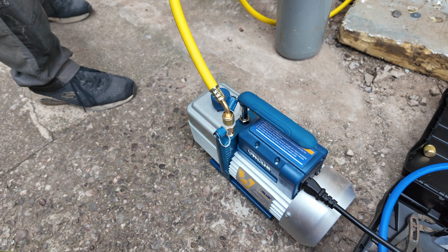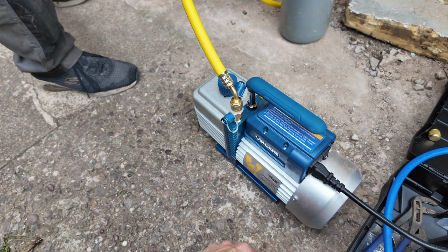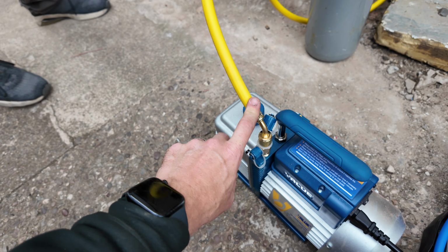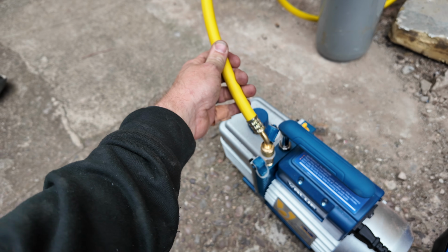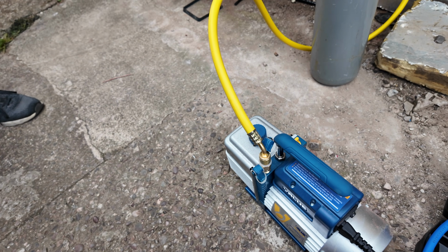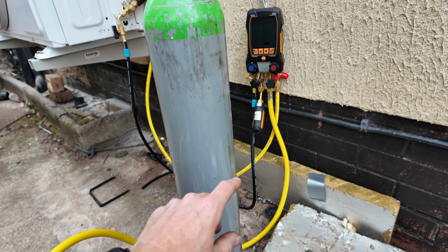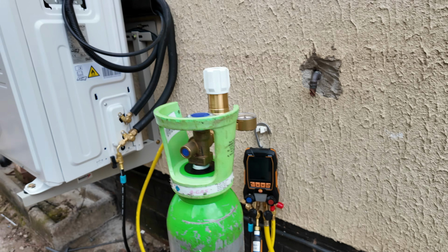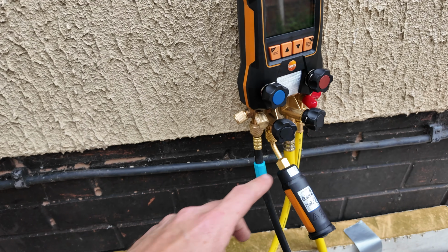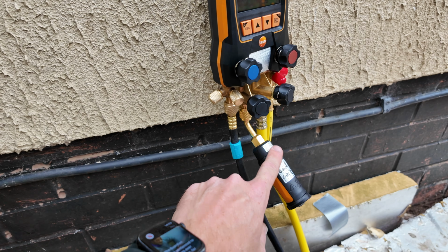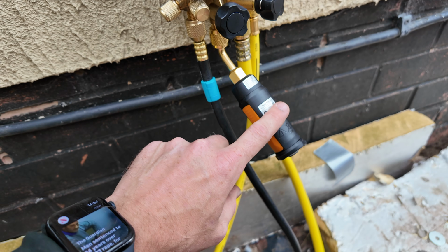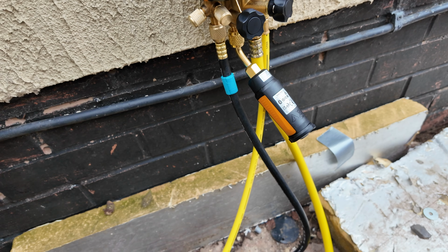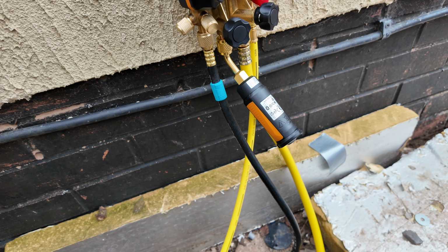This is our little vacuum pump that we got, a Value vacuum pump. You've got one hose from here, it's a big bore hose because it'll give you a better vacuum and a quicker one. So we've got that connected to the middle right gauge on your Testo, and that's open now. Then we've got the vacuum gauge here, that's all on the app, and that's connected to there.